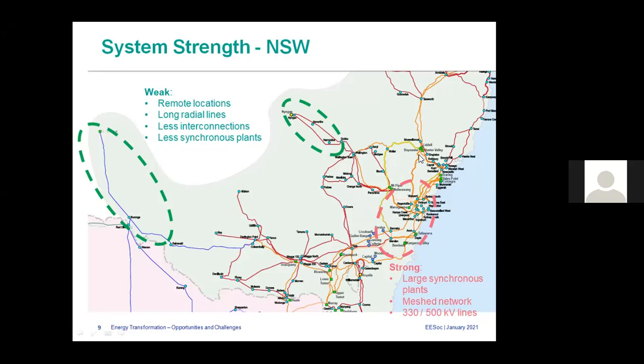You can see a number of coal power stations, these green squares. And then also Eraring, Wallerawang, and like that, they are coal power stations. And then Mount Piper. So many coal power stations near Sydney, and many lines as well. So if you calculate the fault level near Sydney at the bus bar, it's about 15 GVA or 15,000 megawatt MVA. So a fairly high fault level or fairly strong location. But if you go further away to the west, where I have marked these green circles, they are very weak locations.